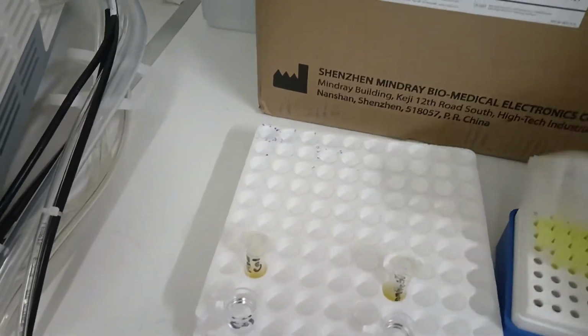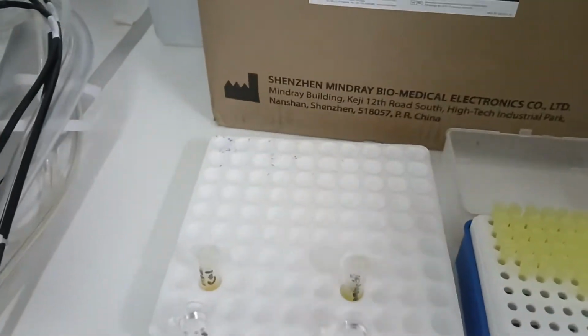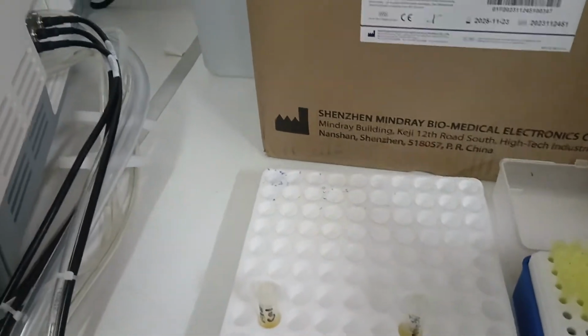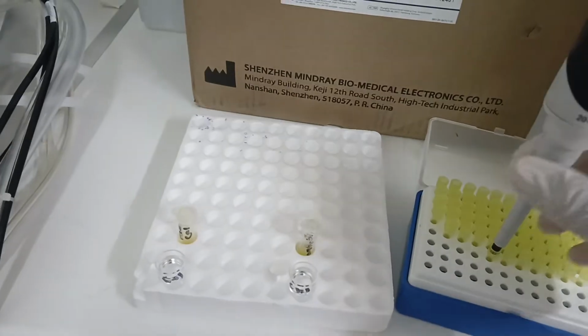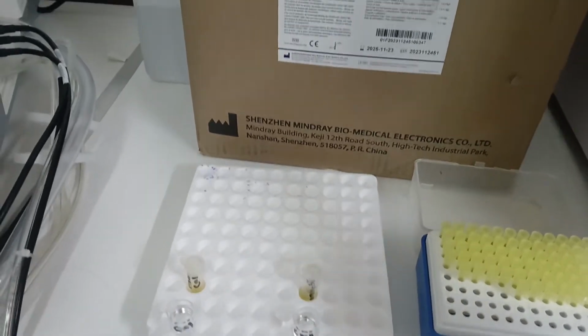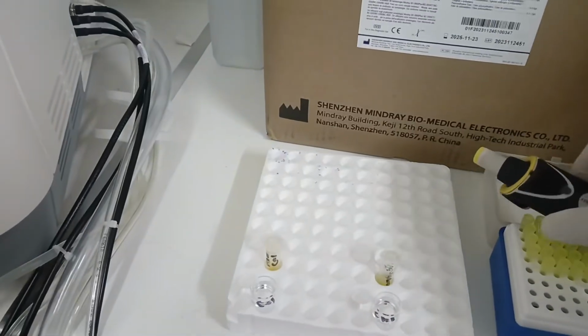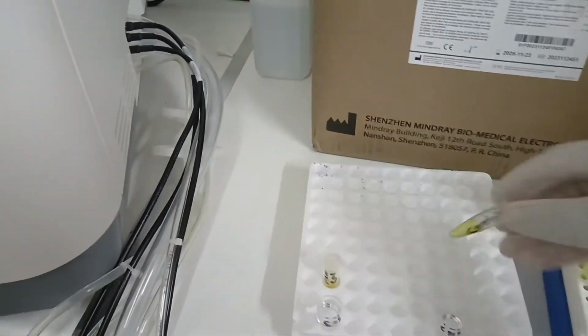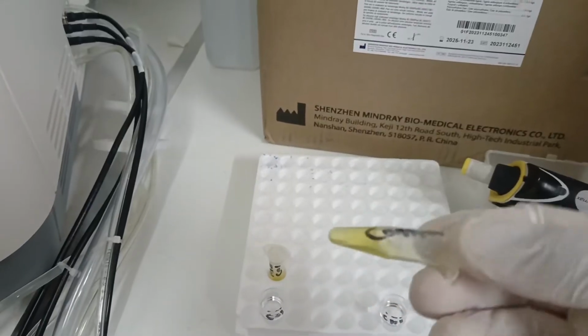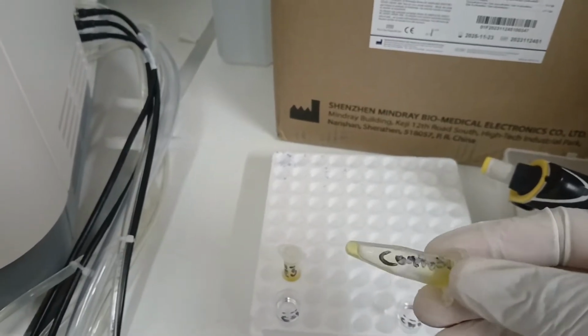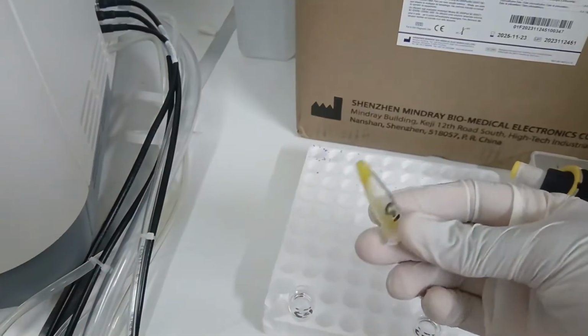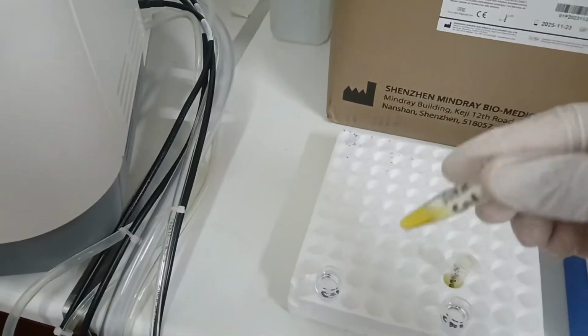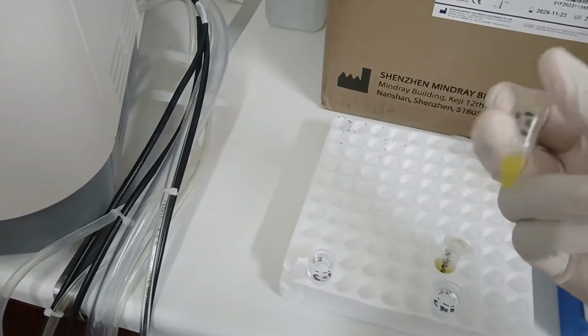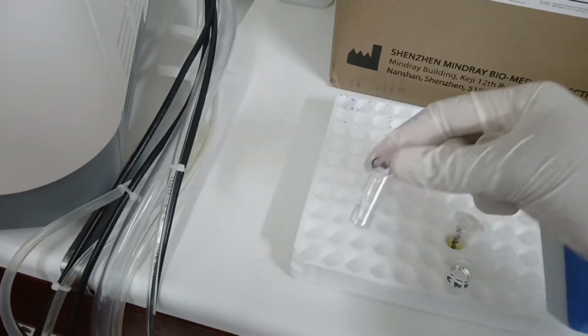Okay, so from here we turn our attention to our calibrator and control. We have them ready. By this time they would have fully thawed, and so we need to transfer an amount, anything from 300 microliters and above, into our microtube, and then from there we can transfer into the machine. You can see our control is fully thawed. It's ready for use, and so is our calibrator. It's well thawed, and then we can pipette some into our microtube and use.